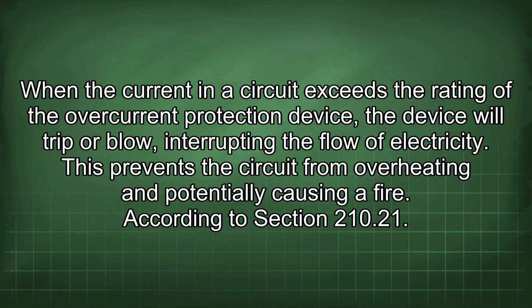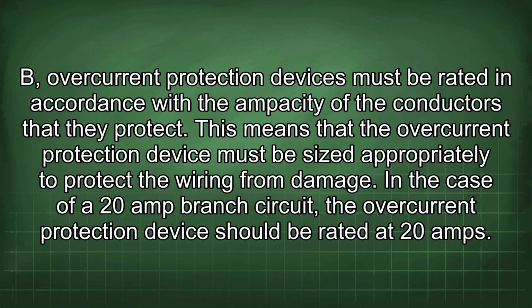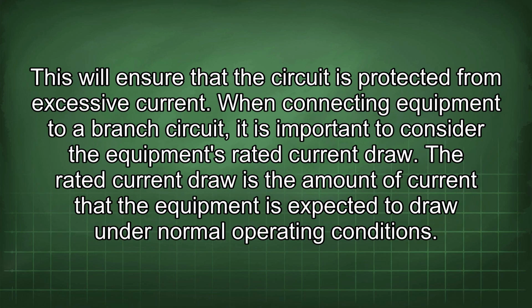According to Section 210.21(B), overcurrent protection devices must be rated in accordance with the ampacity of the conductors that they protect. This means that the overcurrent protection device must be sized appropriately to protect the wiring from damage. In the case of a 20 amp branch circuit, the overcurrent protection device should be rated at 20 amps. This will ensure that the circuit is protected from excessive current.